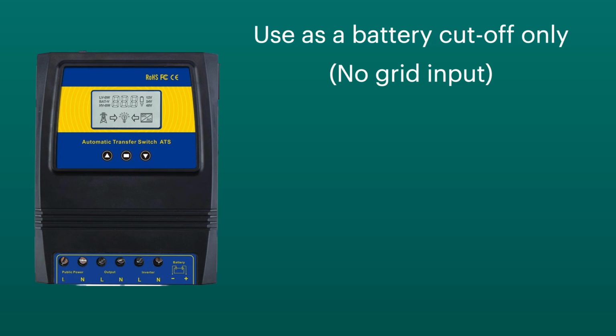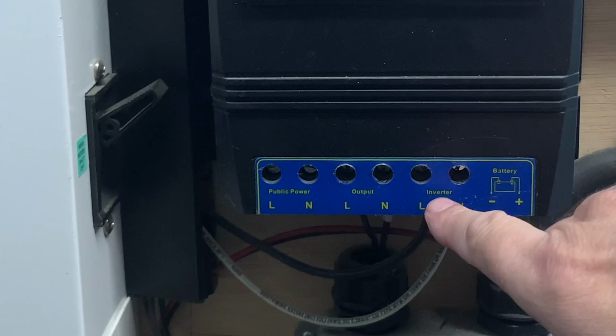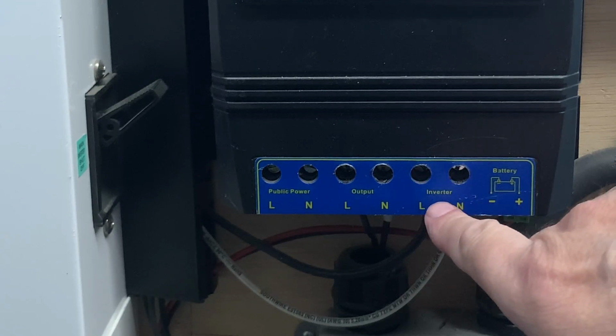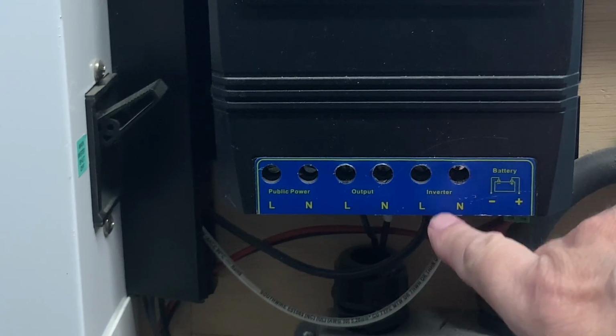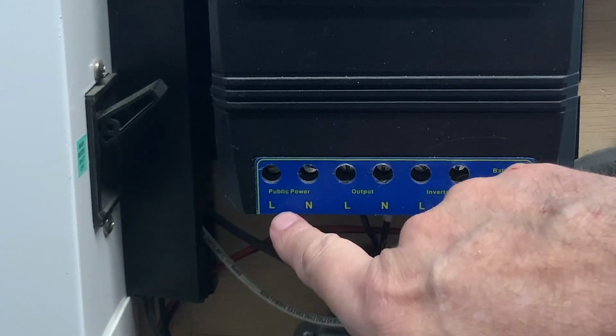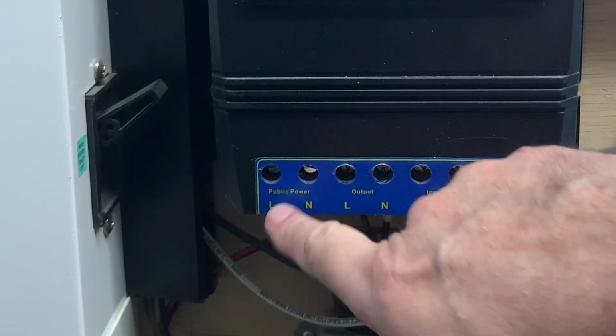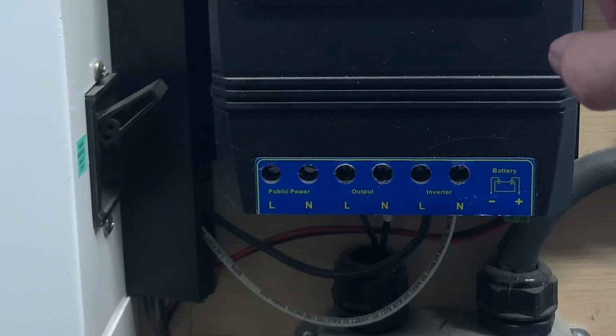There are some safe ways to use this MOES automatic transfer switch. And I think the safest thing to do is just use it as a battery cutoff switch. So you only hook up the inverter side of the inputs and do not connect anything to the grid inputs. And that's what I did when I used this with my early system, as I used the inverter input, but not the grid inputs. I have no wires at all connected over here to the grid input.